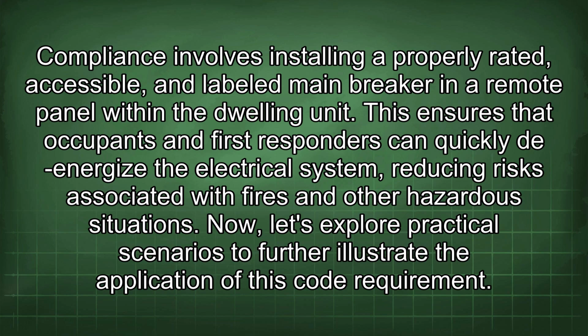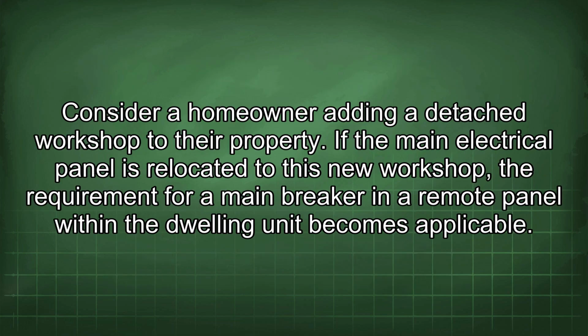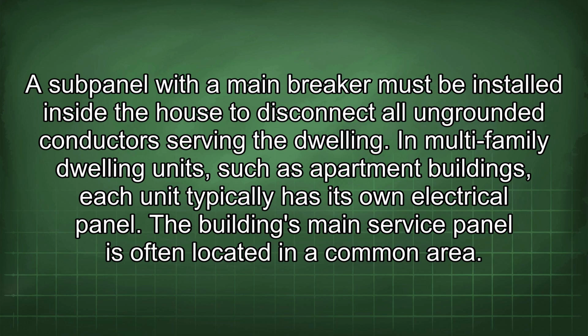This ensures that occupants and first responders can quickly de-energize the electrical system, reducing risks associated with fires and other hazardous situations. Now let's explore practical scenarios to further illustrate the application of this code requirement. Consider a homeowner adding a detached workshop to their property. If the main electrical panel is relocated to this new workshop, the requirement for a main breaker in a remote panel within the dwelling unit becomes applicable. A subpanel with a main breaker must be installed inside the house to disconnect all ungrounded conductors serving the dwelling.